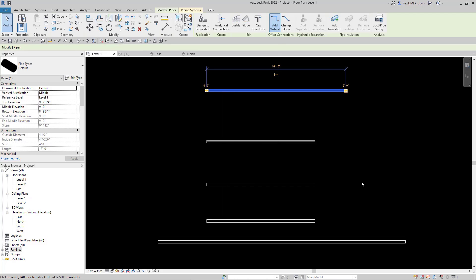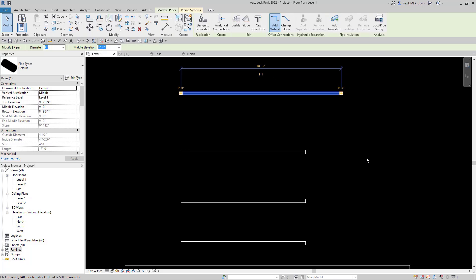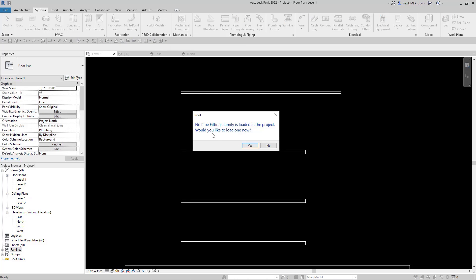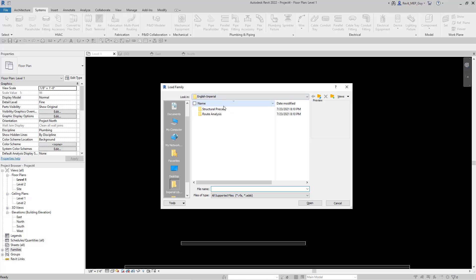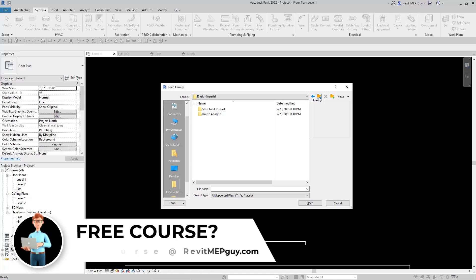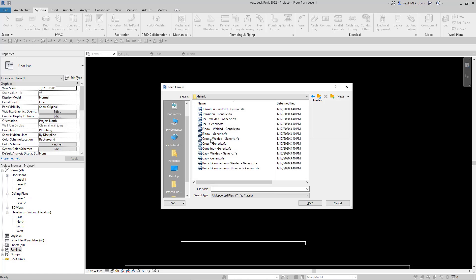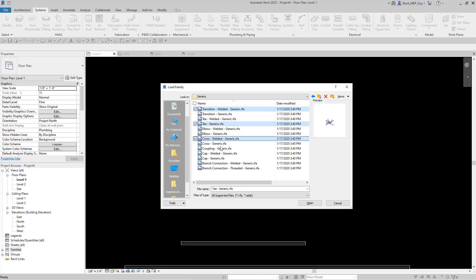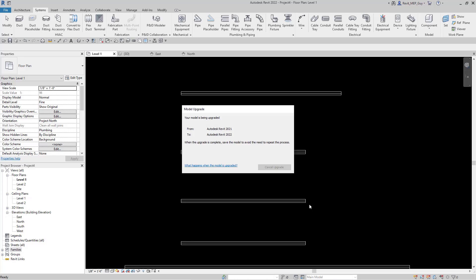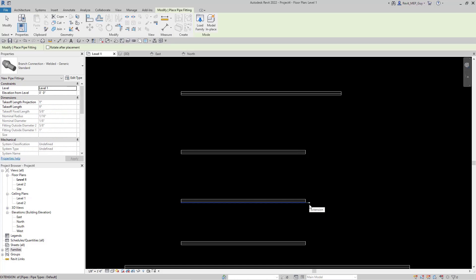I have to load these fittings into my project before I can start to draw pipe. What we could do is go back to Pipe Fittings and this time click Yes. Now we have to search through our computer to find wherever the pipe fittings are located. They are in Revit 2021 Libraries, English Imperial, under Pipe Fittings — and for this I'll use Generic. I can hold down the Control button to select multiple ones, or hit the top and hold Shift to select all of them and load all of these in at once. Revit's going to take a while to load all of these fittings — I'll fast-forward the video to show you how long it takes. Revit finally finished loading all the fittings, so they should be in my project now.